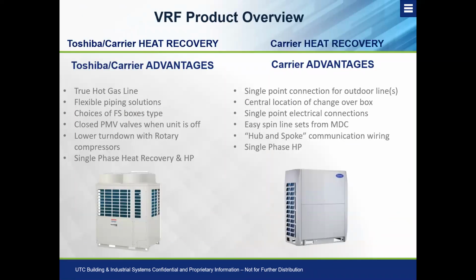Okay, so we talked about a lot. We talked about our Toshiba Carrier heat recovery and heat pump. We talked about our Carrier heat recovery. So let's try to summarize this the best we can. Let's look at the Toshiba Carrier advantages. We talked about having a true hot gas line, where the separation process occurs at the outdoor unit, which is why we call this the heat recovery three-pipe system. We have flexible piping solutions with multiple different styles of selector boxes, single port or multi-port, that you can have. Our PMVs or EXVs are shut 100% when our indoor units are off.